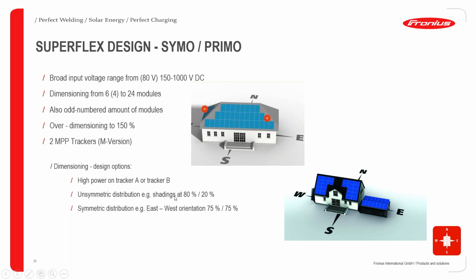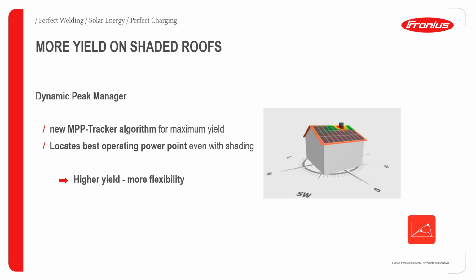As you can see, by so doing, it doesn't have any effect on the inverter. Of course, it produces evenly and outputs power optimally. And then we can also have a symmetric distribution. If you have maybe east-west orientation and evenly distribute the modules equally, this doesn't stop the inverter from operating. It can operate both for unsymmetric and symmetric distribution, which is a very big plus on our inverter capabilities. So let's now talk about more yield on shaded roofs.